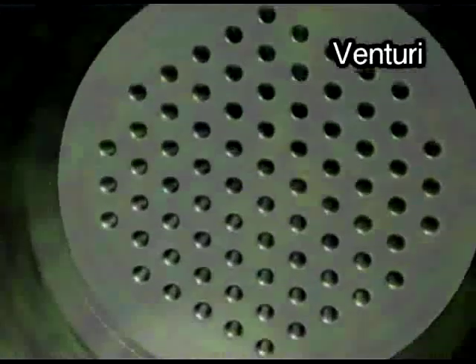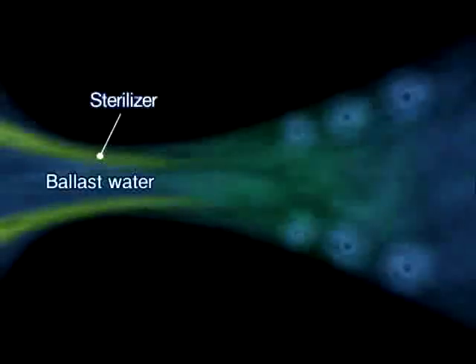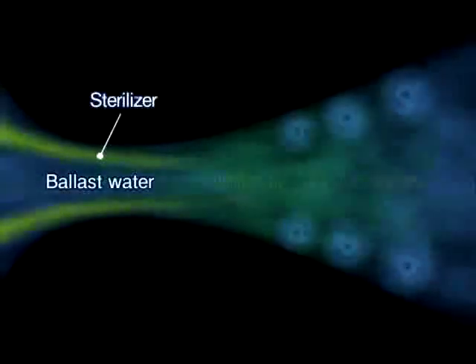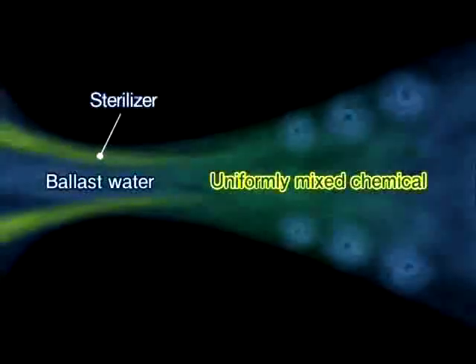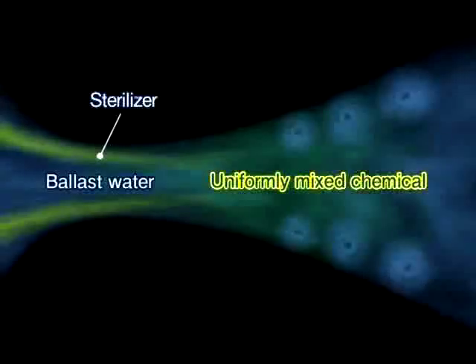Next, the injector injects a disinfectant at a number of points. The venturi system consists of a large number of conical venturi tubes arranged in parallel. The venturi system ensures uniform instantaneous mixing of the disinfectant. In addition, bacteria adhering to sand are separated, heightening the disinfection effect.